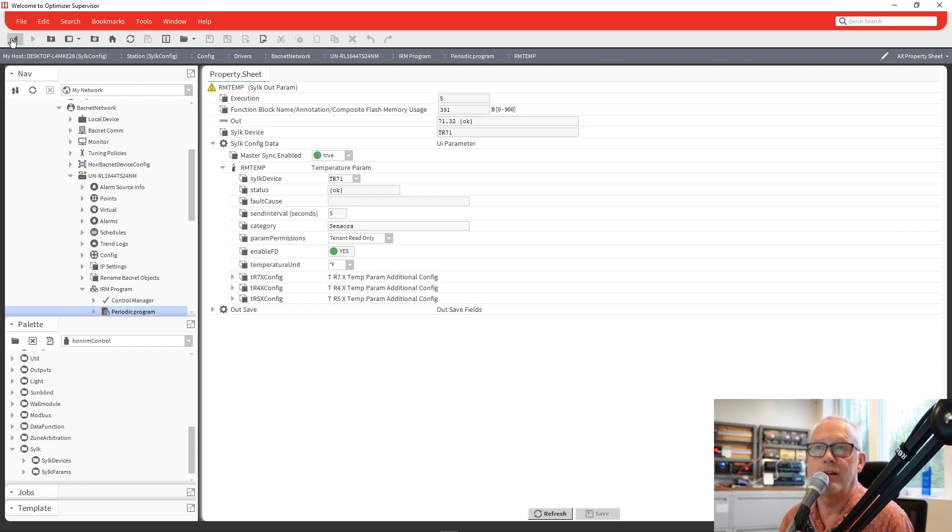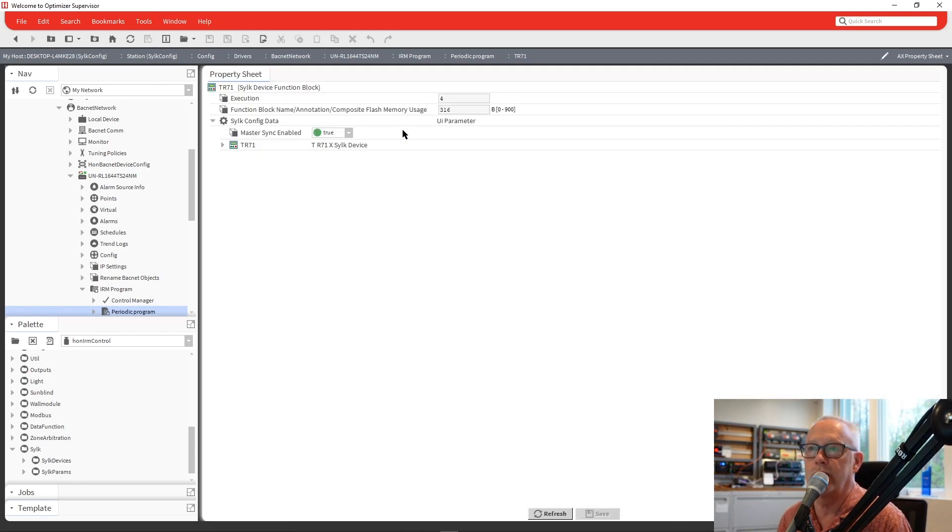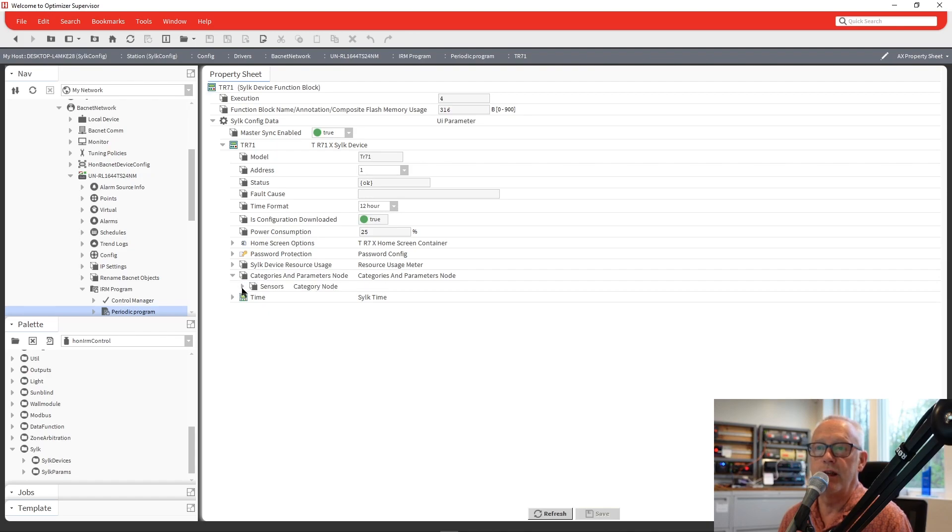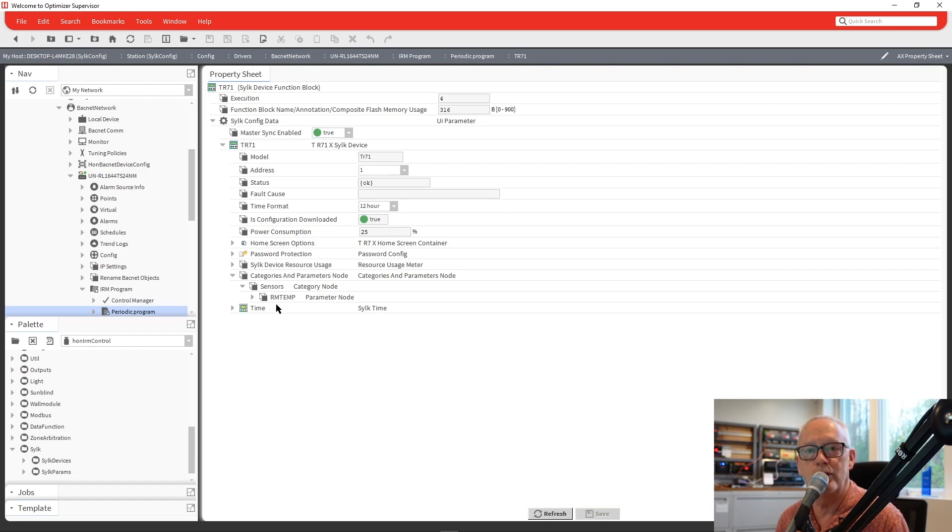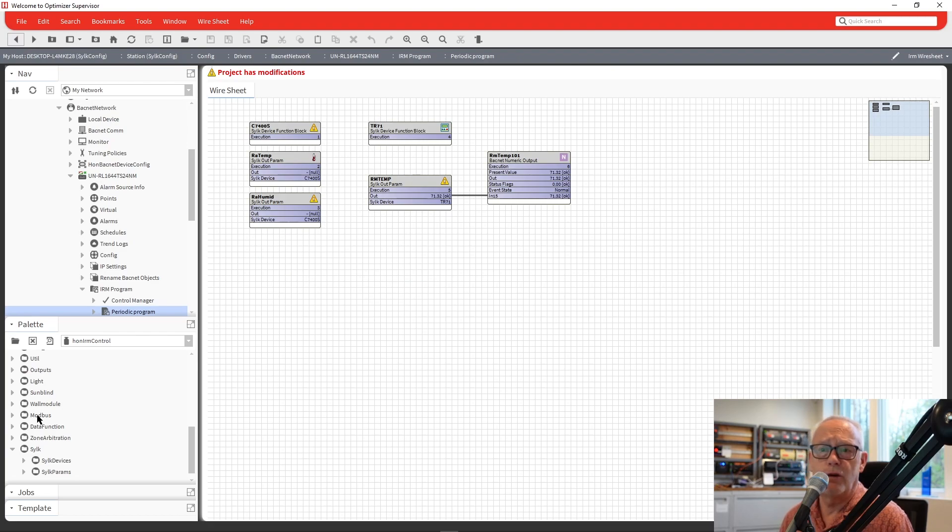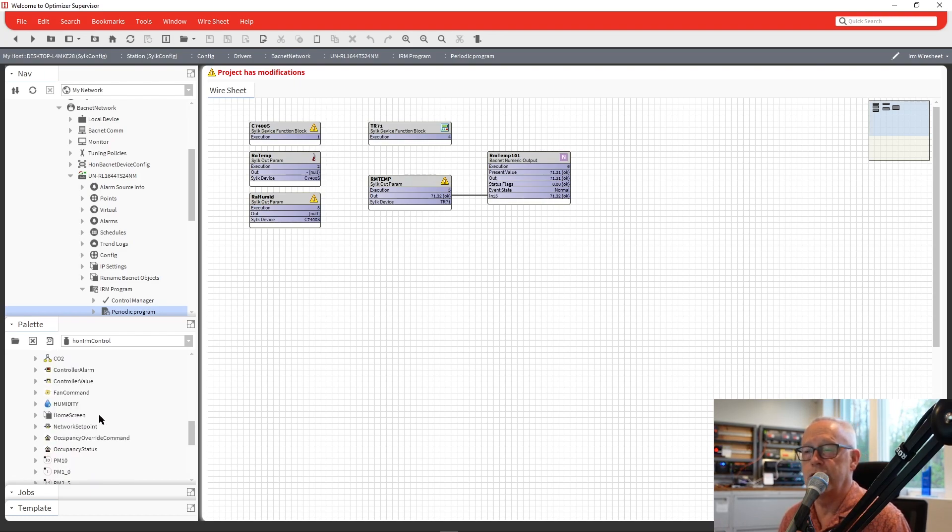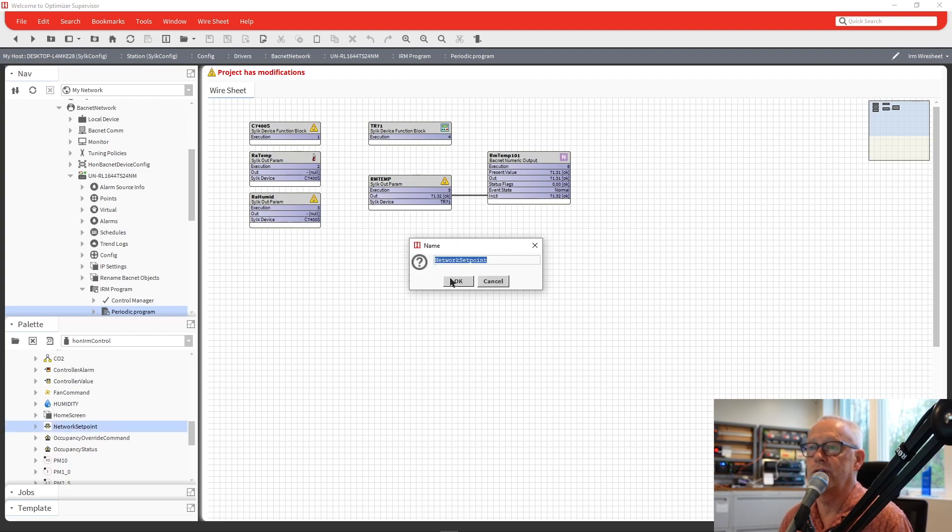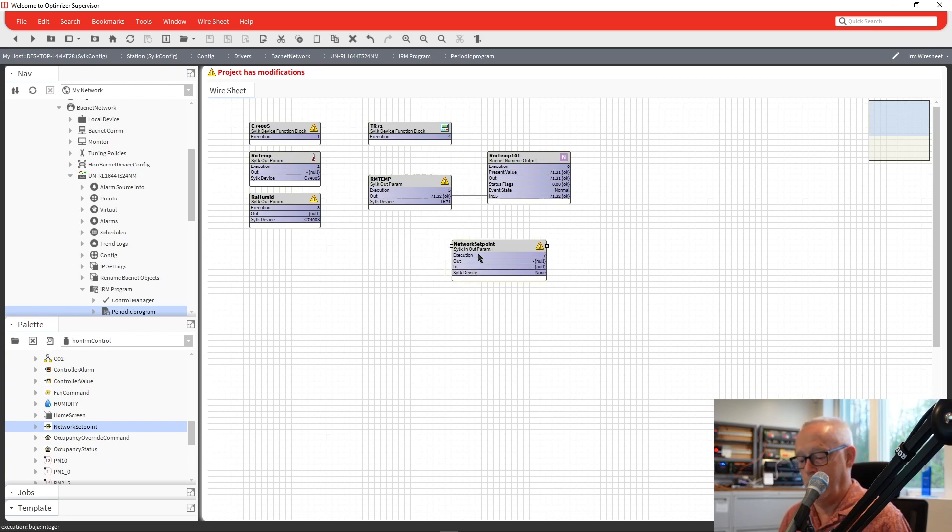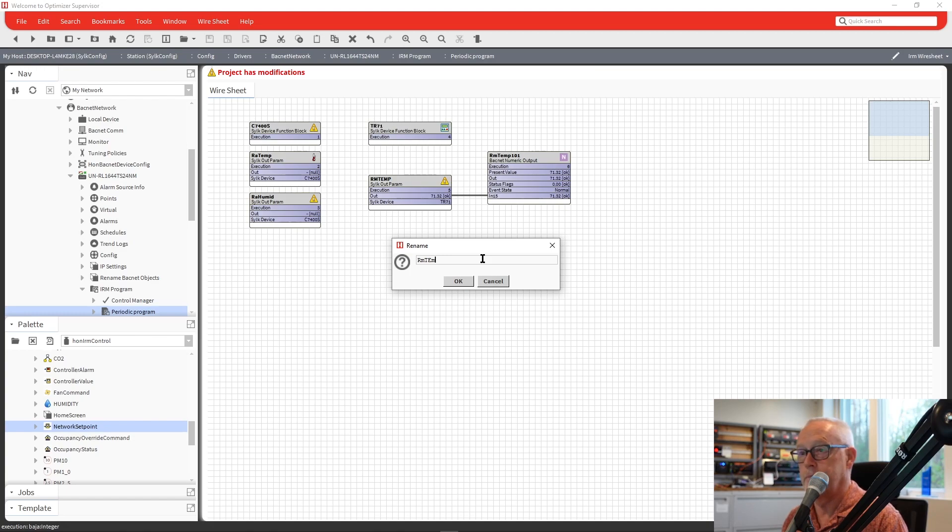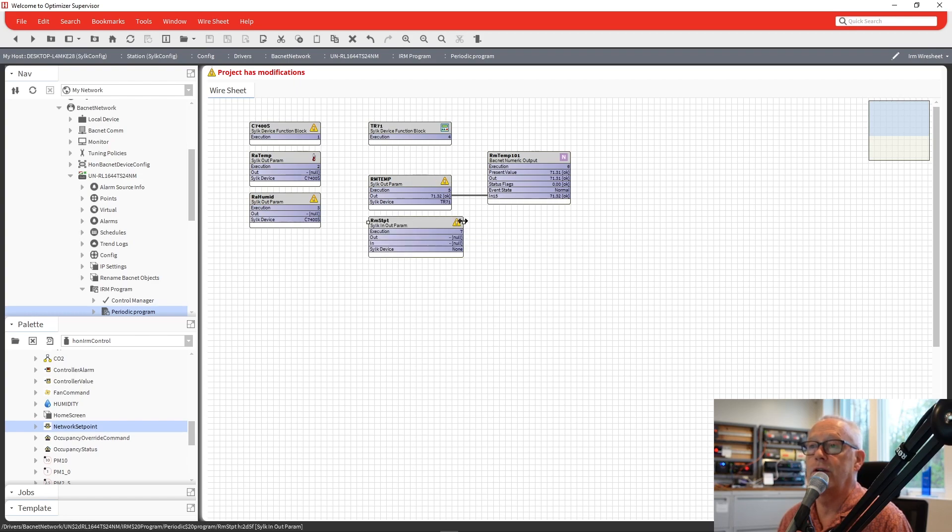So now that we have that in the room temp, if we go back and look at TR71 and we expand that and we look at our categories and parameters, you'll see in there we do have a category called sensors. And right now, room temp is the only device that's under that. So if we continue on with that and we go back down to our palette under the HON IRM control and look at our parameters, we could go in there and let's say, we'll add a set point. So if we go in and we do a set point in here for this device and we'll actually call it room set point.